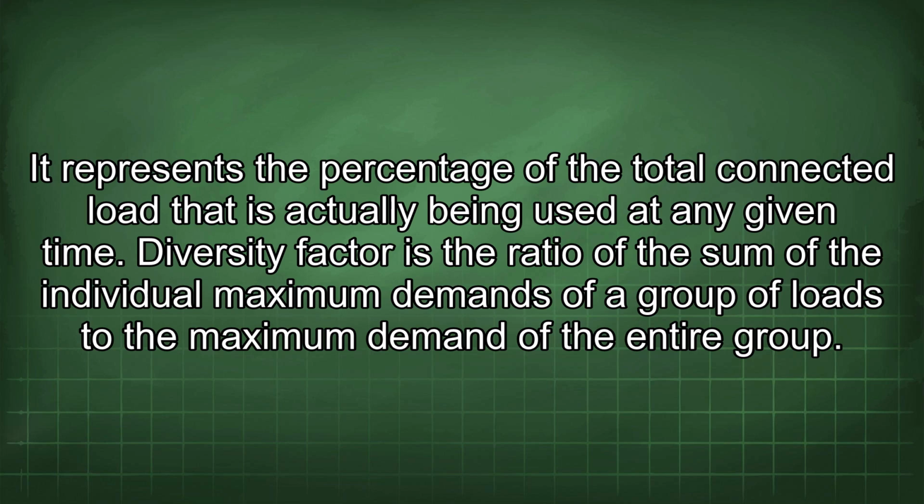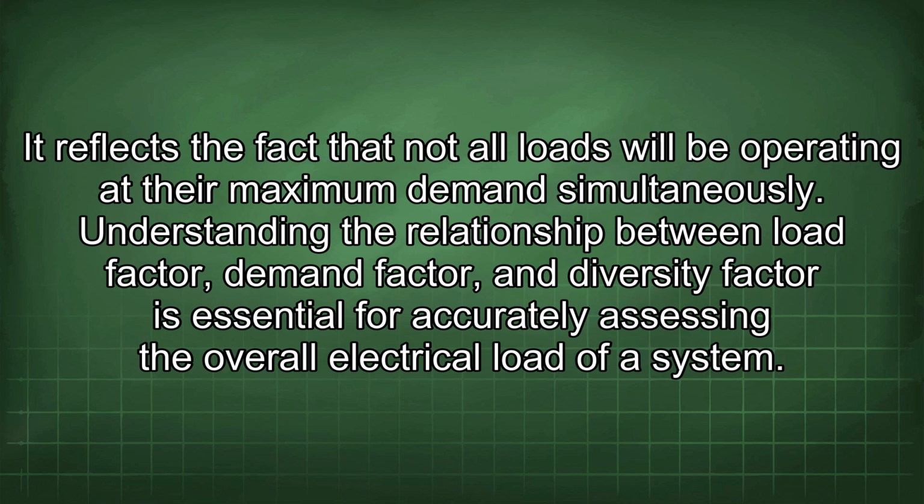Diversity factor is the ratio of the sum of the individual maximum demands of a group of loads to the maximum demand of the entire group. It reflects the fact that not all loads will be operating at their maximum demand simultaneously.